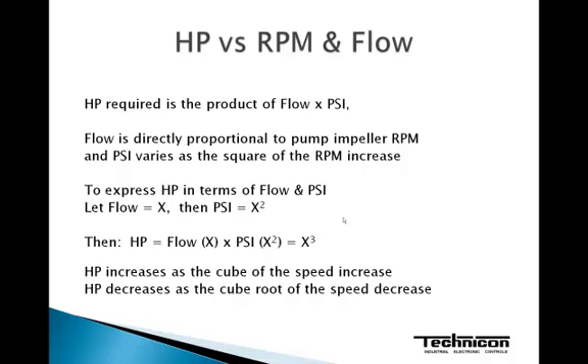So if we look at horsepower versus RPM and flow, we know that horsepower required is the product of flow times the PSI in the system. Flow is directly proportional to the pump impeller RPM, and the pressure or PSI varies as the square of the RPM increase.